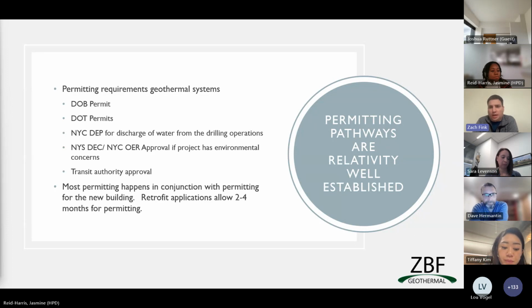There are DOB permits, typically filed as part of the mechanicals; if the bore fields are filed separately, it's usually an earthwork permit. You may need DOT permits, whether to cross a mapped street with a pipe for district systems, or to temporarily place a storage tank or frac tank for drilling on the street, or for drilling access. DEP permits cover discharge of water from drilling, similar to a site dewatering permit. You might also need DEC or OER approval depending on environmental concerns, and you might need transit authority approval.